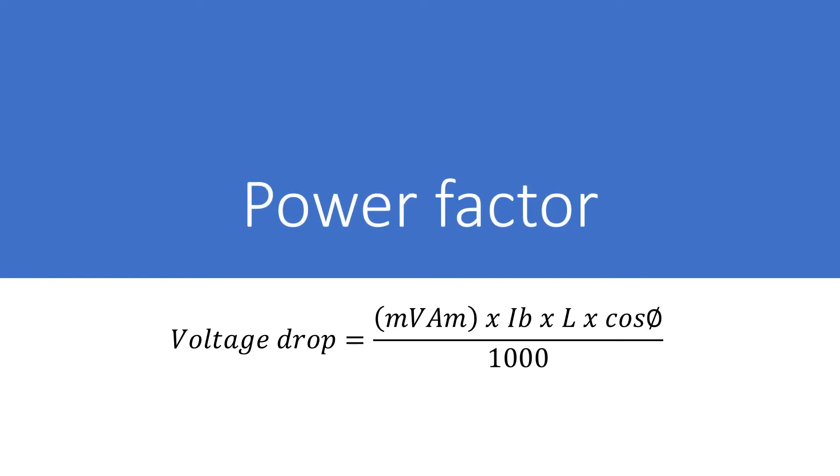So where the power factor is known for a circuit, we can take this into account in the voltage drop calculation. So the equation becomes voltage drop equals millivolts per ampere per meter multiplied by design current, multiplied by length, multiplied by power factor and then divided by 1000.